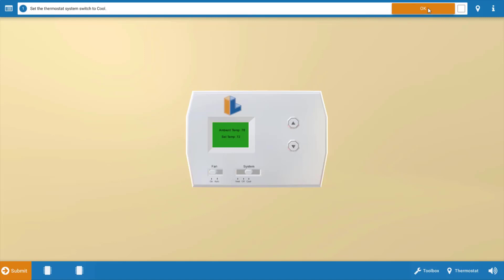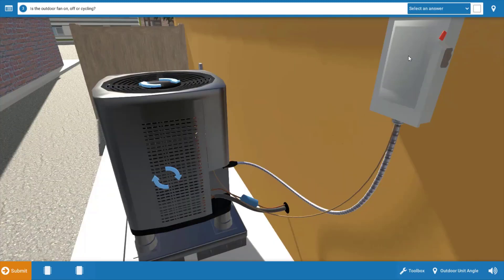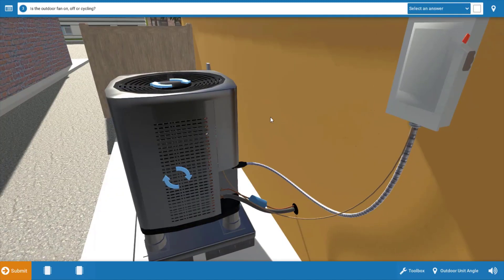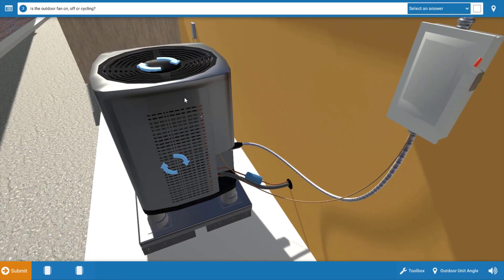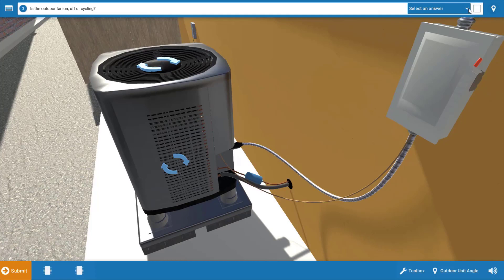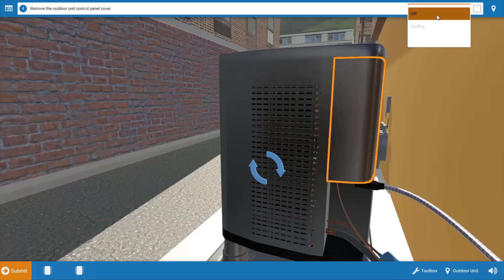Click okay on the procedure guide at the top and we're going to assess which electrical loads are operational. We can see here that our indoor fan is running, so we're going to click yes. But when we get to the outdoor unit, we see that our outdoor fan motor or our condenser fan motor here in the top is not running. So on our menu up here we're going to say it's off.